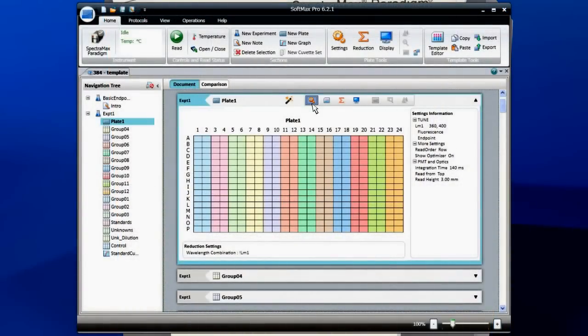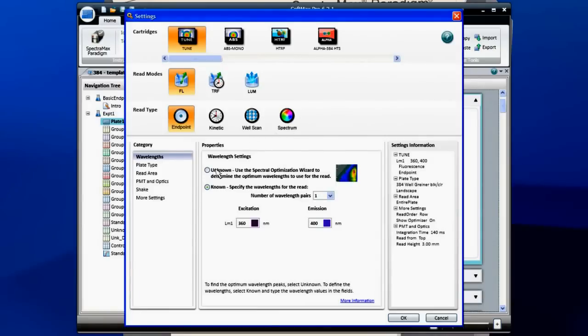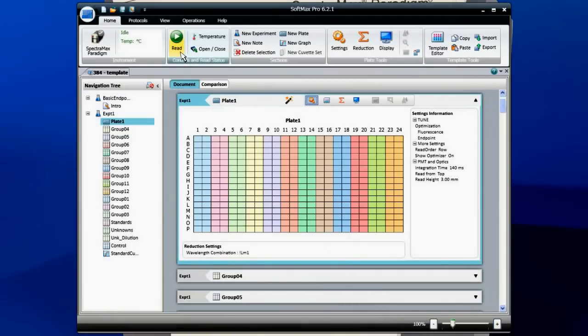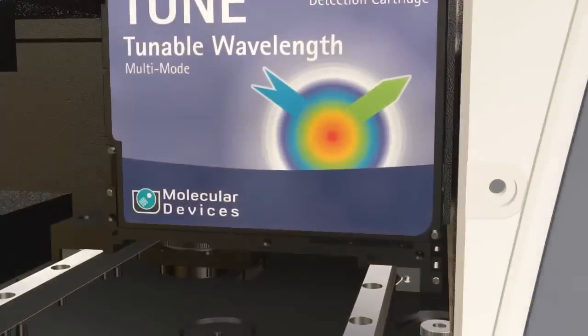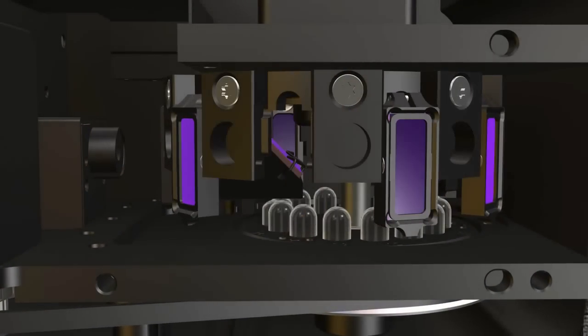but also offers powerful data analysis features. The breakthrough technology in the TUNE cartridge combines the 1nm wavelength flexibility of a monochrometer with the sensitivity of filters, while offering up to 10 times more sensitivity than other monochrometer-based systems.